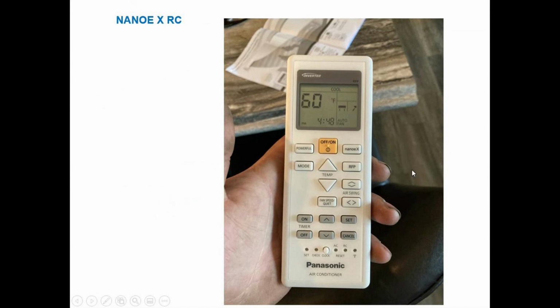Then take your remote controller and press just once for 1 second and leave it. Press and leave it. You hear another beep. If you do not hear another beep, repeat this process. You must hear a beep, and if you hear the beep, that means your error code is gone, erased, and you can go back again and check if it's truly erased. So you must get one beep here and one beep over here at your remote controller. So the check button is over here, guys. So obviously you need a toothpick or a very thin prong, like a multimeter probe or something like that, to push and hold that check button there.